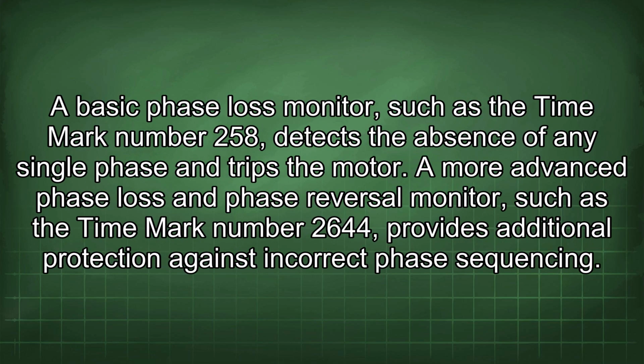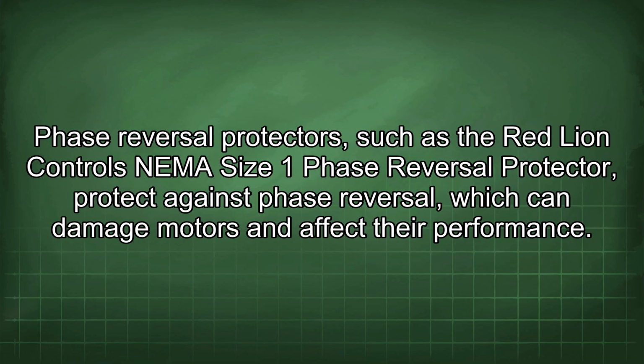A basic phase loss monitor, such as the Timemark number 258, detects the absence of any single phase and trips the motor. A more advanced phase loss and phase reversal monitor, such as the Timemark number 2644, provides additional protection against incorrect phase sequencing. Phase reversal protectors, such as the Red Lion Controls NEMA Size 1 Phase Reversal Protector, protect against phase reversal, which can damage motors and affect their performance.